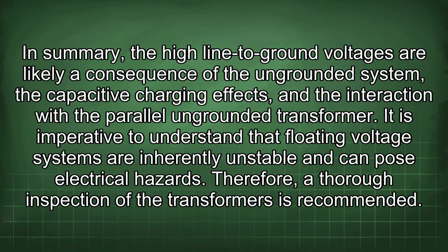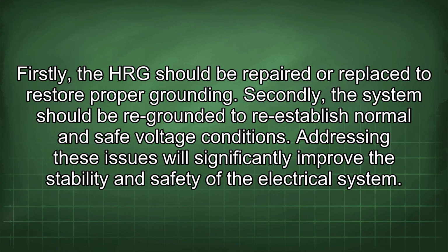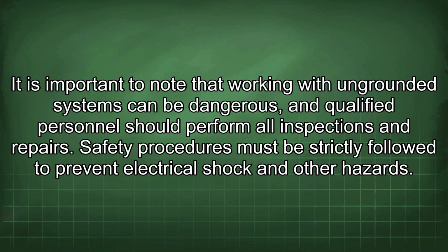It is imperative to understand that floating voltage systems are inherently unstable and can pose electrical hazards. Therefore, a thorough inspection of the transformers is recommended. Firstly, the HRG should be repaired or replaced to restore proper grounding. Secondly, the system should be re-grounded to re-establish normal and safe voltage conditions. Addressing these issues will significantly improve the stability and safety of the electrical system. It is important to note that working with ungrounded systems can be dangerous, and qualified personnel should perform all inspections and repairs. Safety procedures must be strictly followed to prevent electrical shock and other hazards.